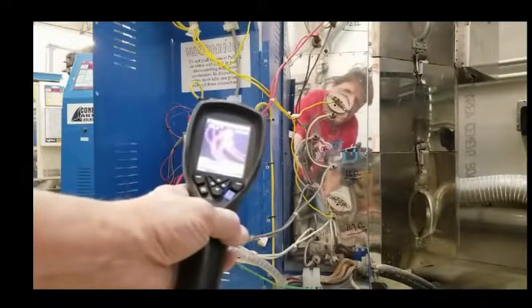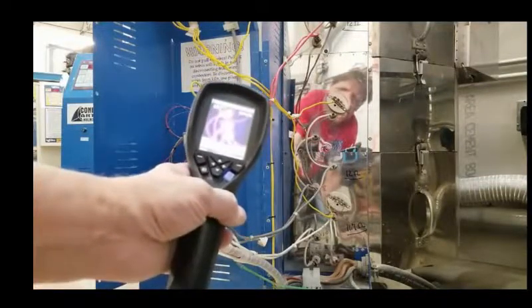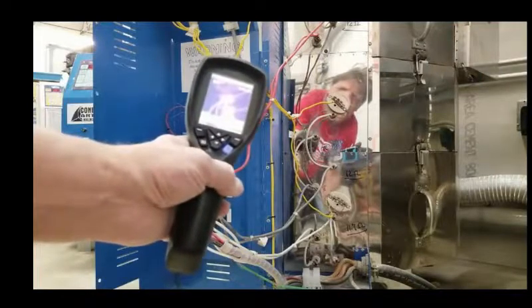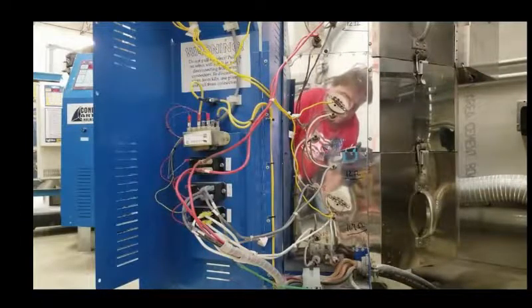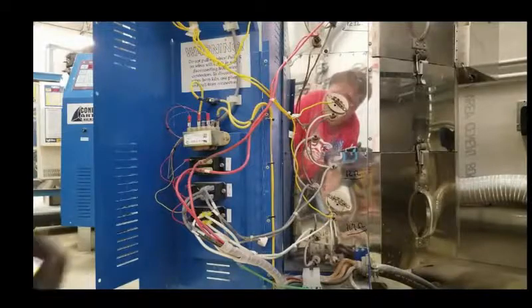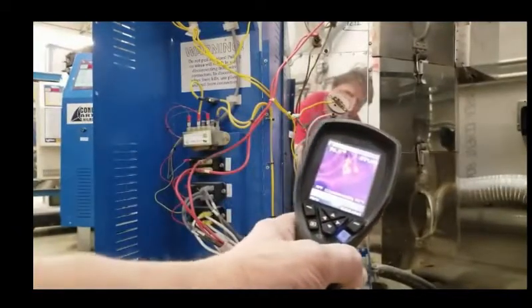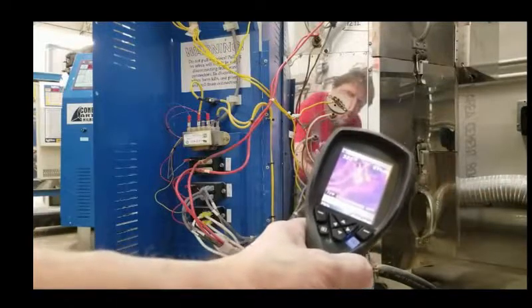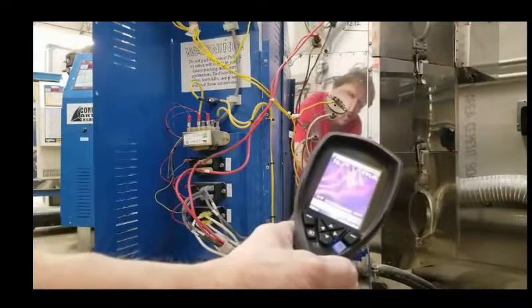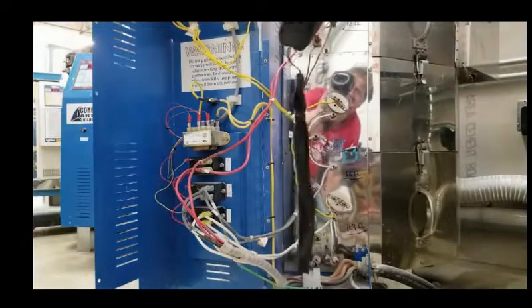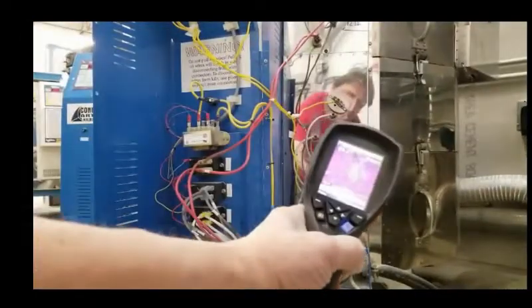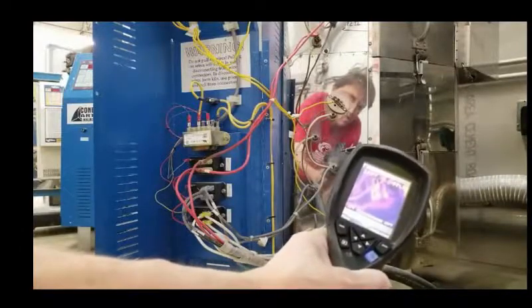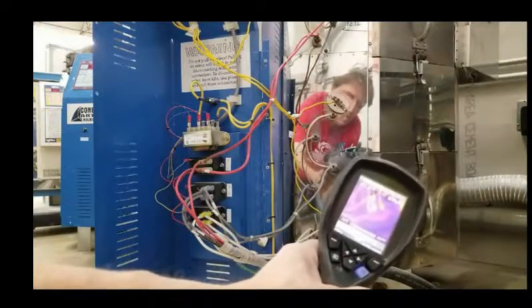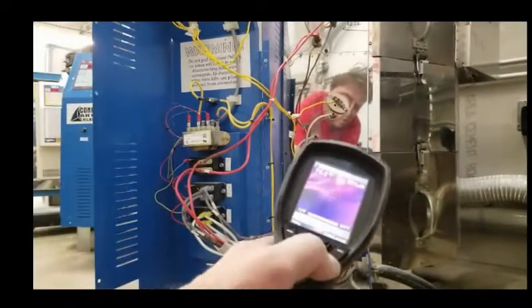This is the coolest one, and if I look, I've got 109, 109, 113-ish, 110 maybe. So they're all operating at the same temperature. That's a plus. As long as I've got this machine with me, I'm going to look around for any super hot spots, and that's kind of warm, but it's only 85 degrees nearby. So that's the end of an element. And as I look at all these, they look pretty good. The one in this very bottom left-hand corner, it looks like I'm going to tighten up once I pull the power off, because it's considerably hotter than the rest.